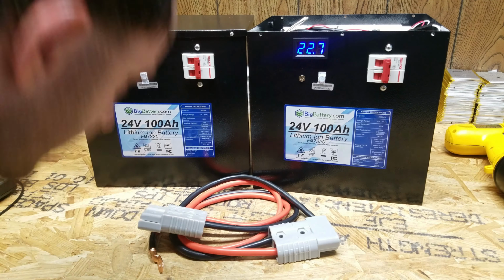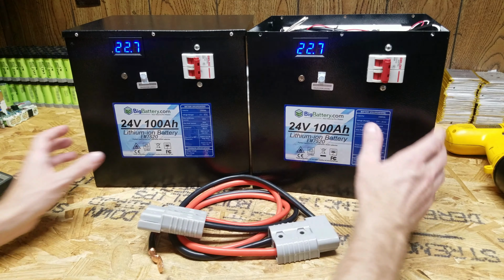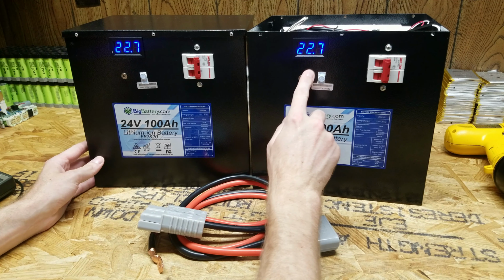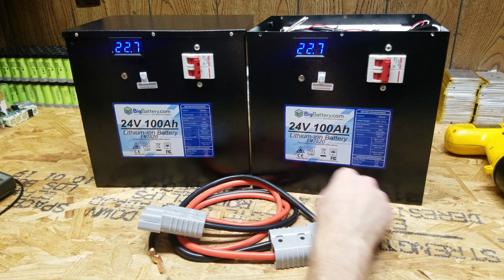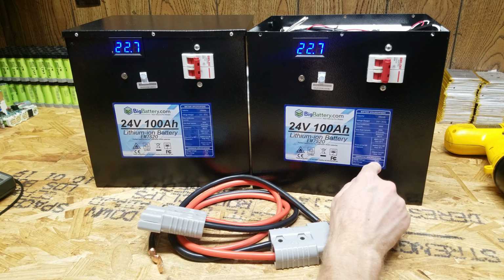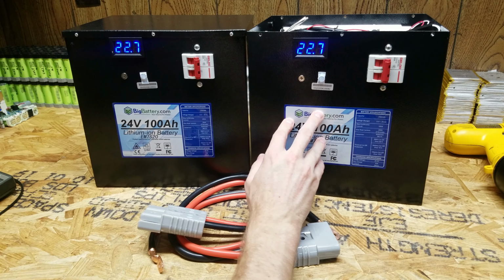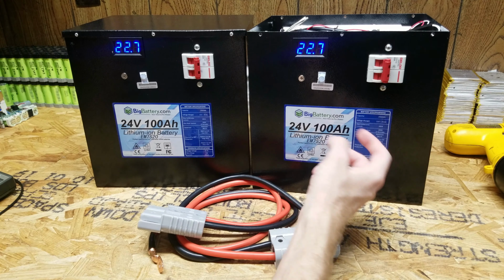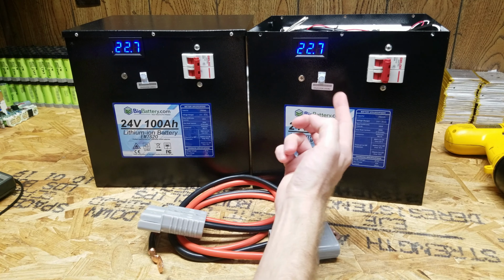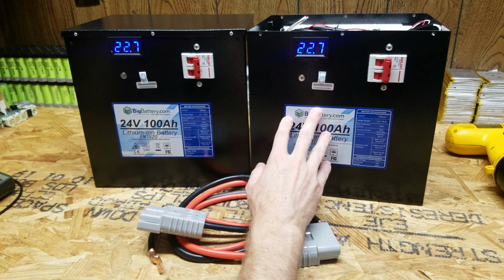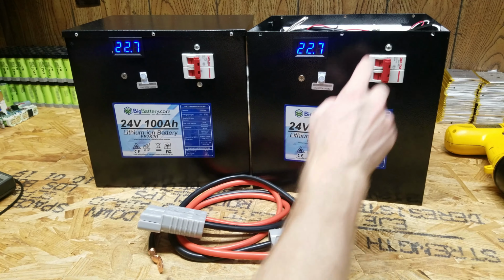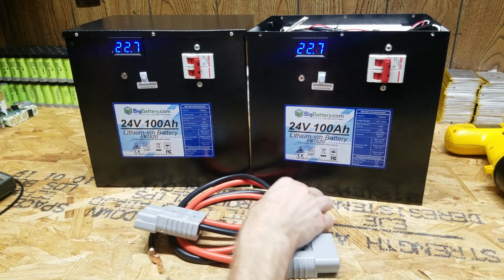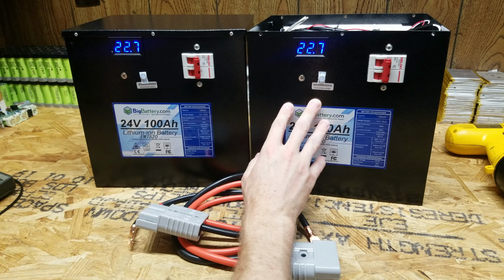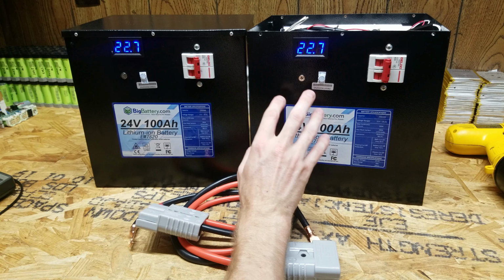However, I think there are a few things we need to keep in mind here. First of all, if you remember, we didn't charge them completely up, because it's difficult to hit that exact charge terminal voltage with the PCM60Xs. When you've got a lot of current charging like that, they tend to throttle down and throttle up. It would have helped if I had the battery sense cables connected from that charger directly to the battery in here, bypassing this cabling. Additionally, the inverter shut down before the batteries actually did.